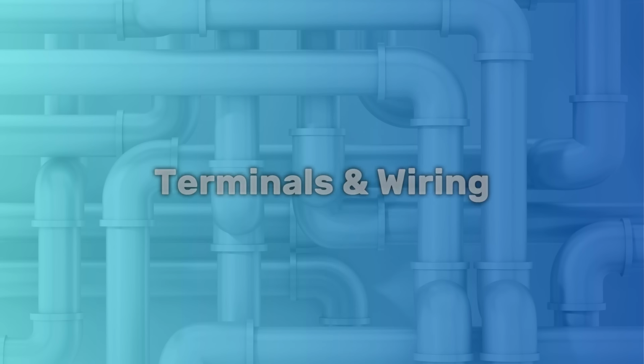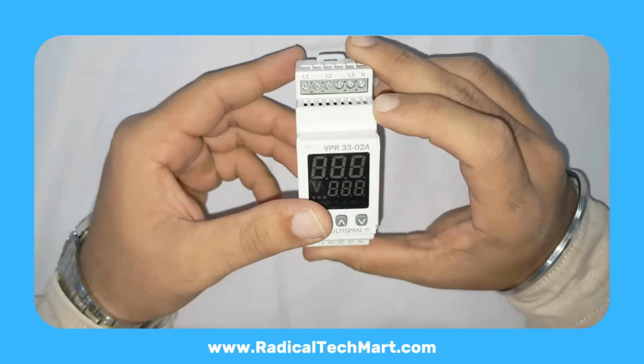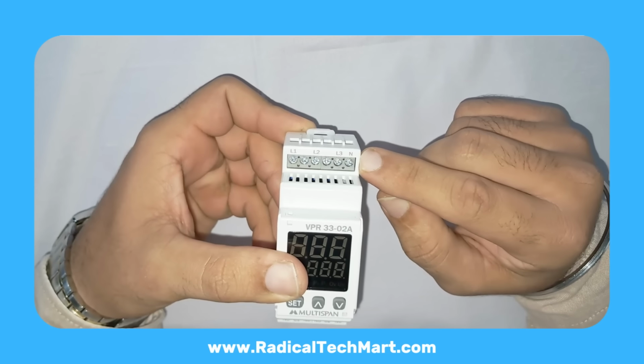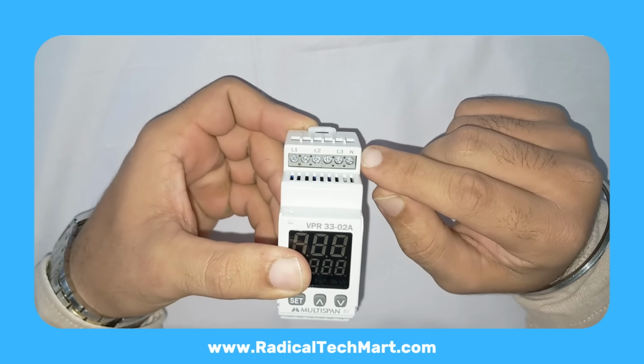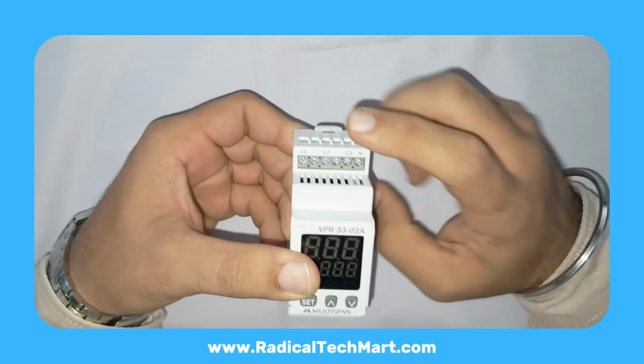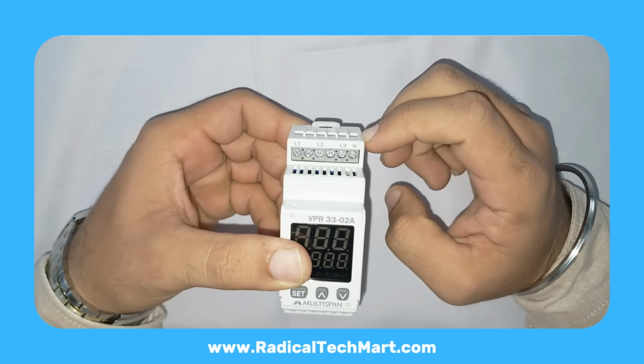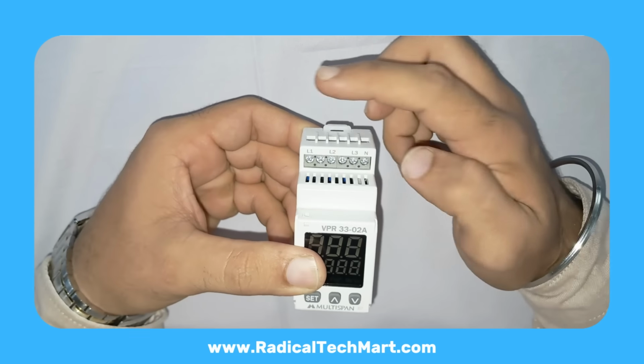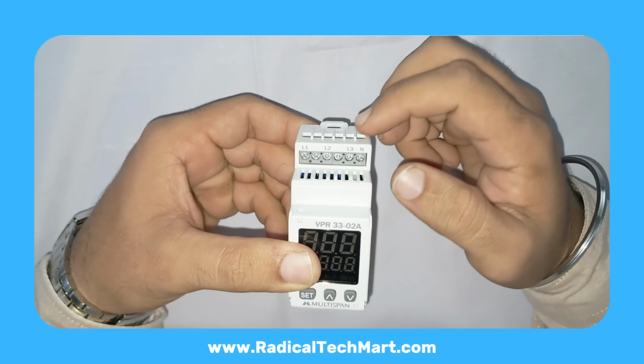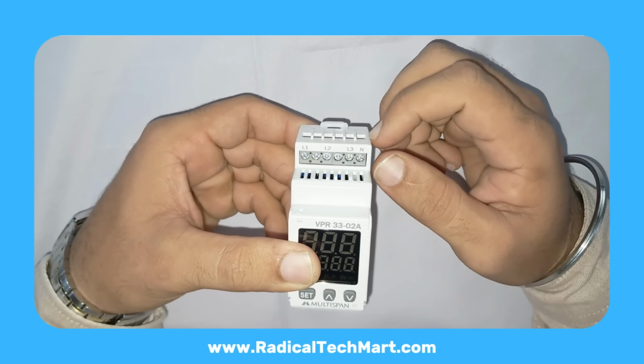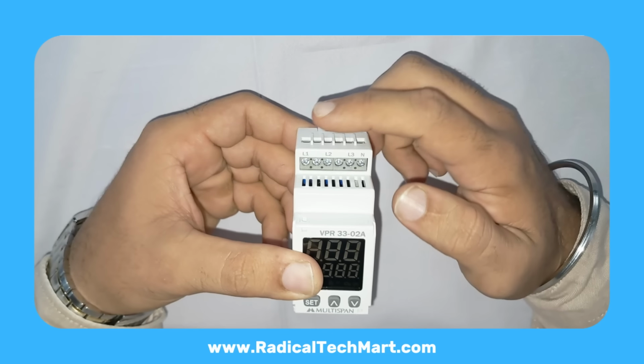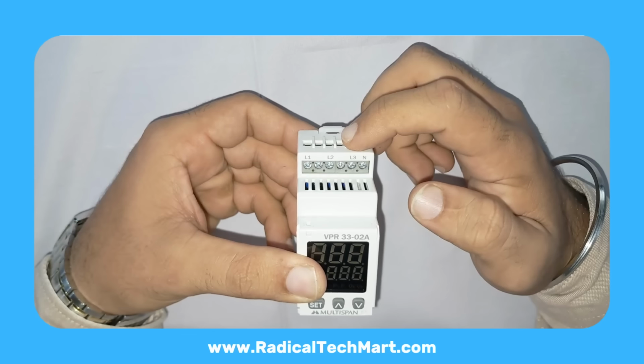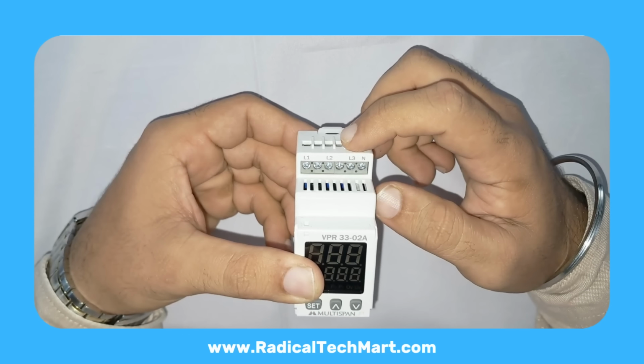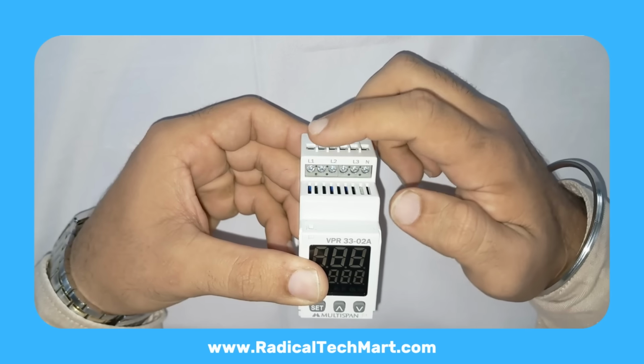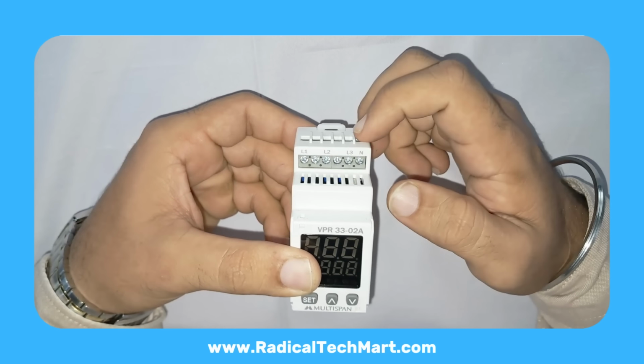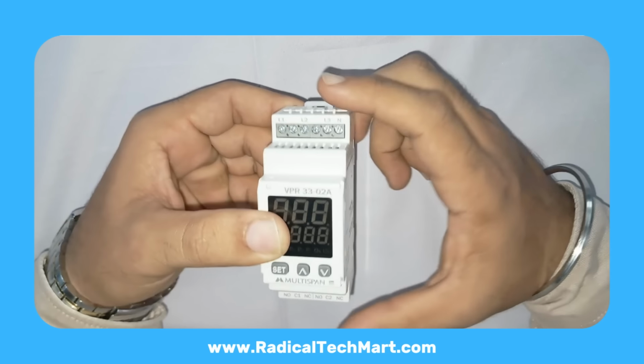Terminals and wiring. Now let's talk about the connections. On the top side, you will see terminals marked L1, L2, L3 and N. Depending on your system, if you have single phase, just connect L1 and neutral. If you have 3-phase, 3-wire, connect R, Y and B to L1, L2 and L3. If it's a 3-phase, 4-wire system, then connect R, Y, B, and neutral. You'll also notice there is isolation between the 3 phases, which makes wiring safer and easier.